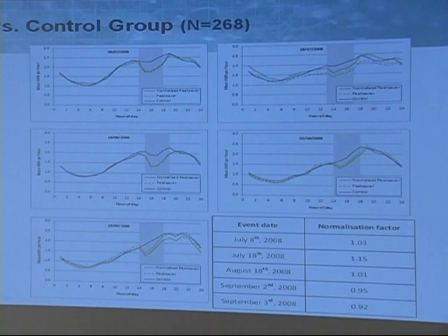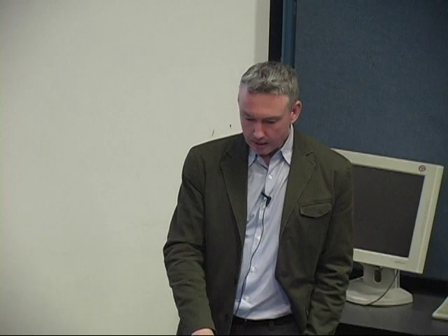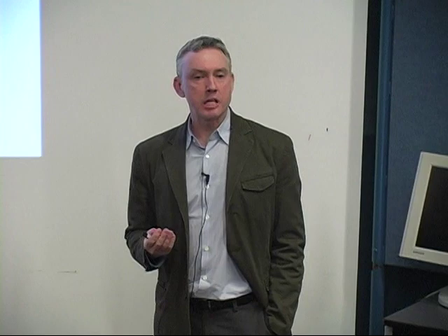You'll notice that on August 18th, the control group's purple line also takes quite a dip during the Peak Saver event. That appears to be because a large storm passed through that day and air temperature dropped dramatically over a couple of hours, causing air conditioner loads in the control group to drop as well. For an equivalent day approach, you'd like to find a day with similar weather, close in the calendar to the event day — which is actually very difficult to do.